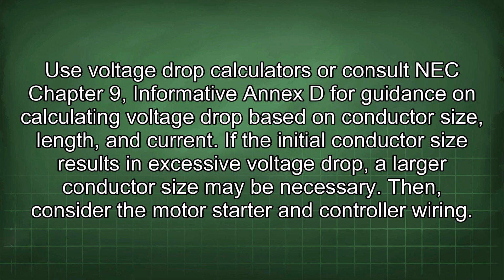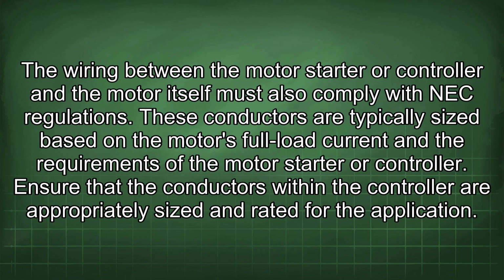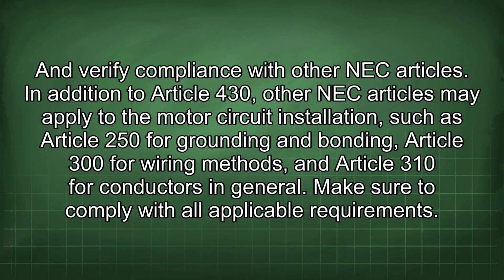Then consider the motor starter and controller wiring. The wiring between the motor starter or controller and the motor itself must also comply with NEC regulations. These conductors are typically sized based on the motor's full load current and the requirements of the motor starter or controller. Ensure that the conductors within the controller are appropriately sized and rated for the application, and verify compliance with other NEC articles. In addition to Article 430, other NEC articles may apply to the motor circuit installation, such as Article 250 for grounding and bonding, Article 300 for wiring methods, and Article 310 for conductors in general. Make sure to comply with all applicable requirements.